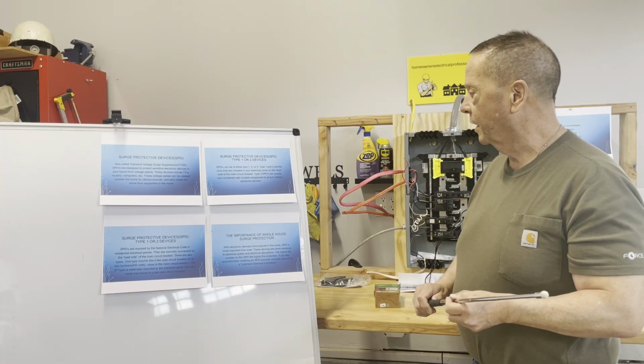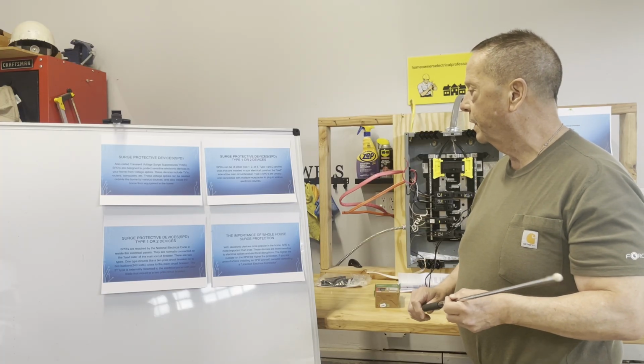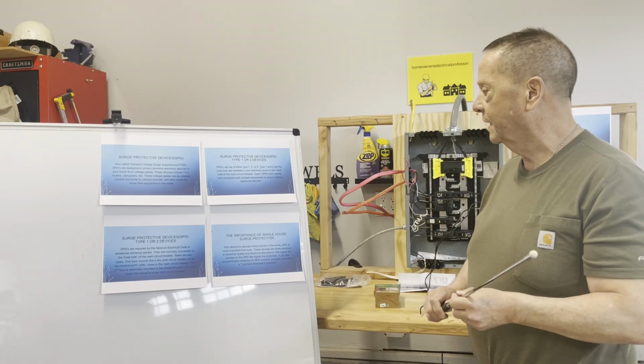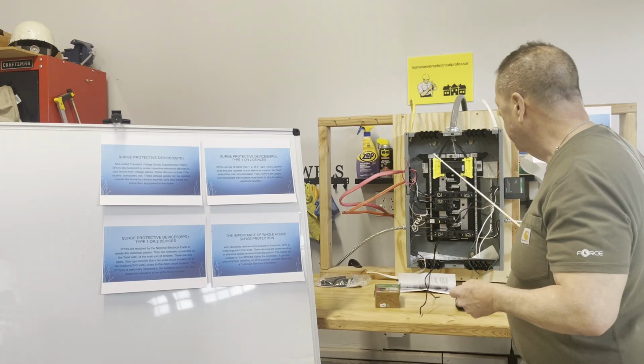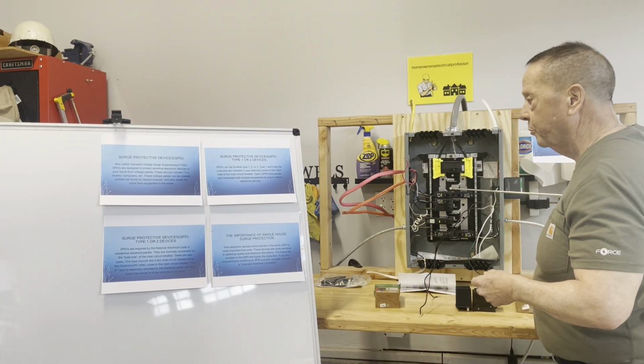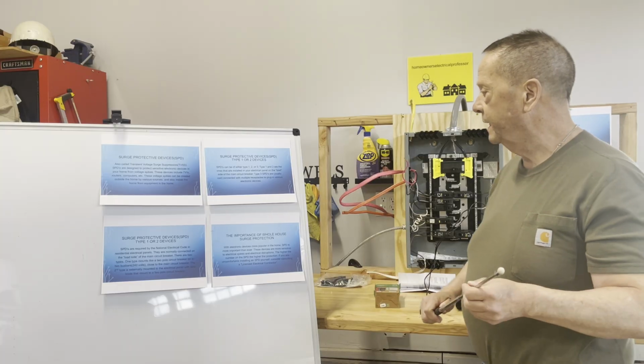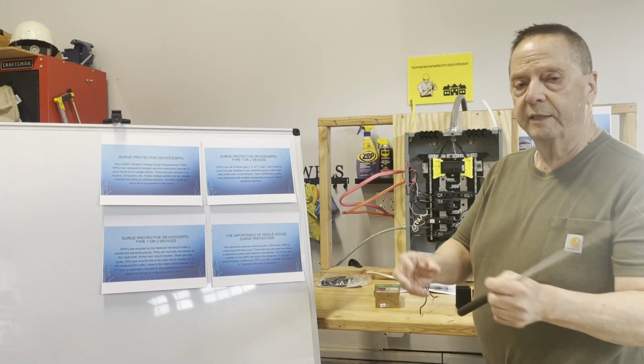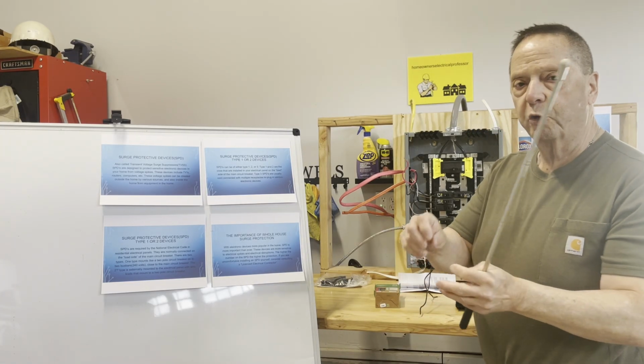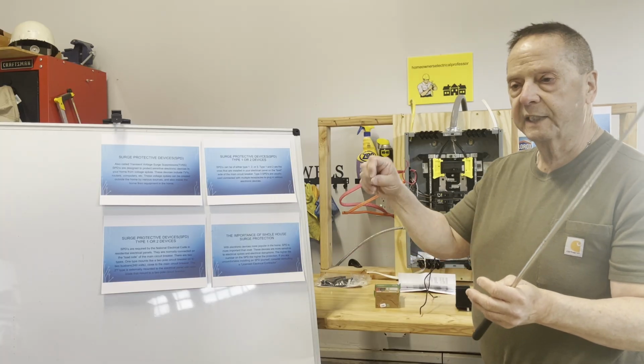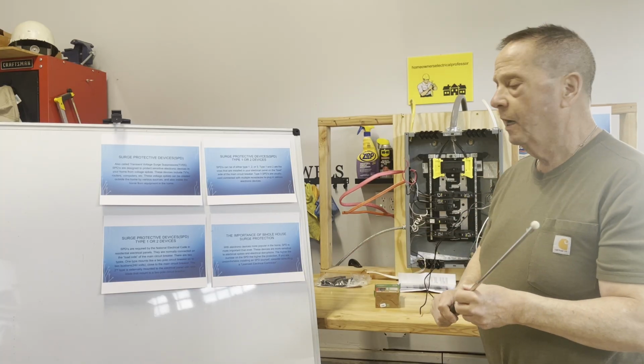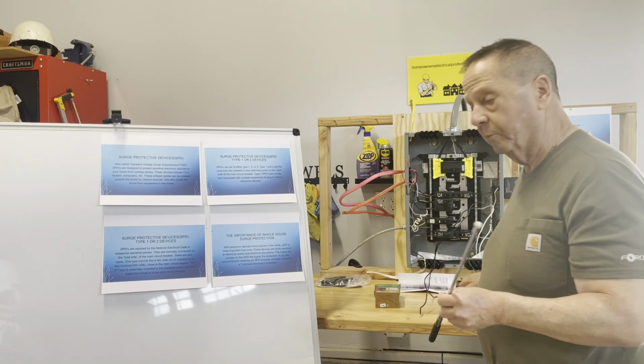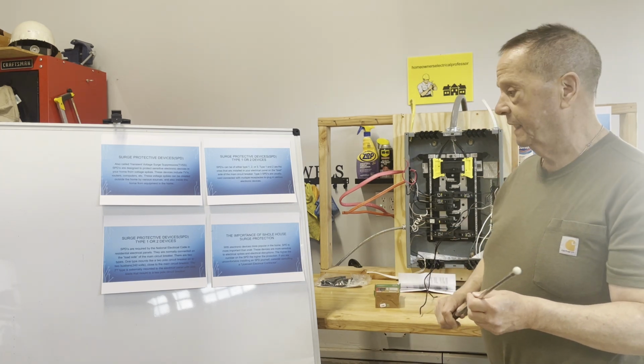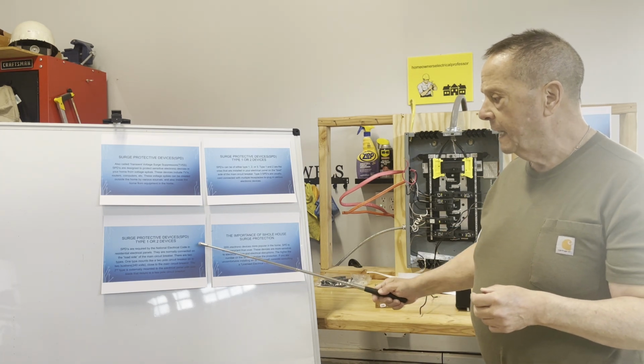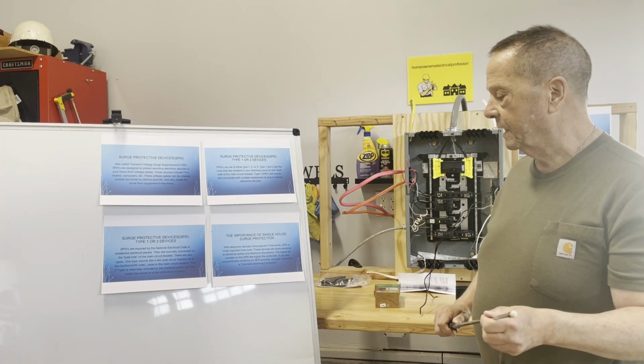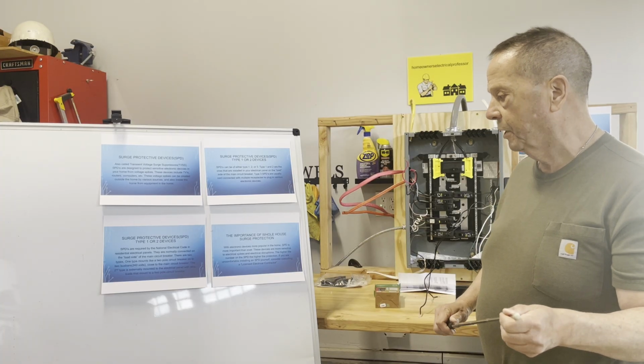They can be either type 1, 2, or 3. Type 1 and 2 are installed in the electrical panel, on the load side of the main circuit breaker down here. Type 3 SPDs are cord connected, like a multi-strip that has surge protection, and it only protects the items you plug into it. A whole house surge protector, like I'm going to show you, protects everything in your house. Nowadays, they're required to be in residential panels by the National Electrical Code.